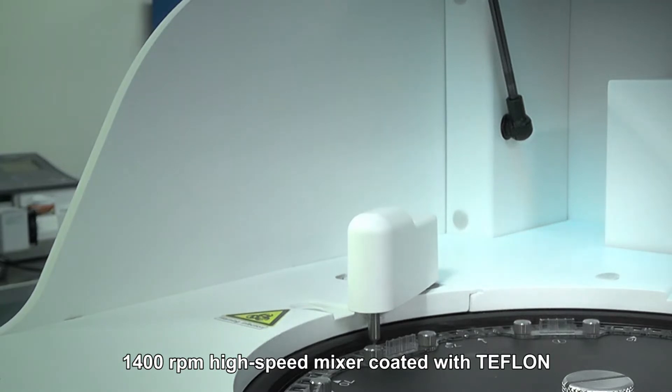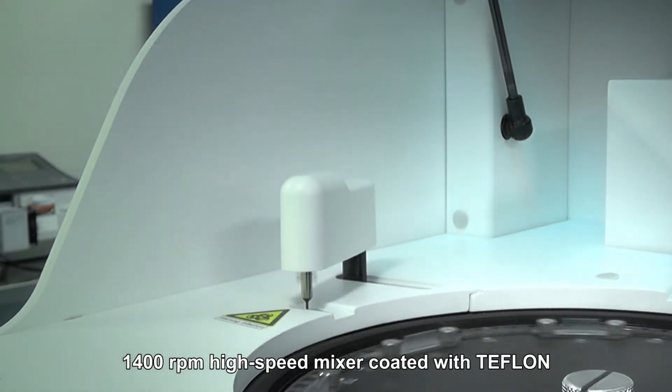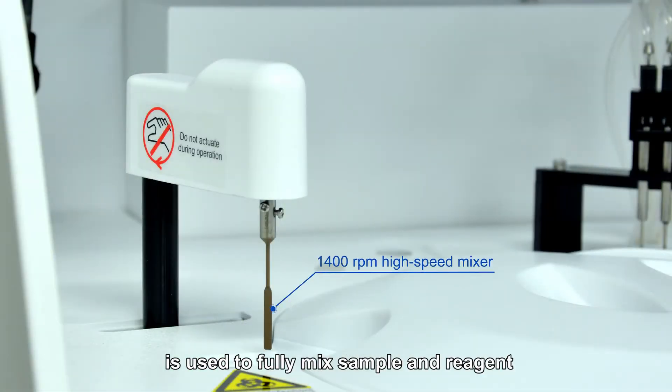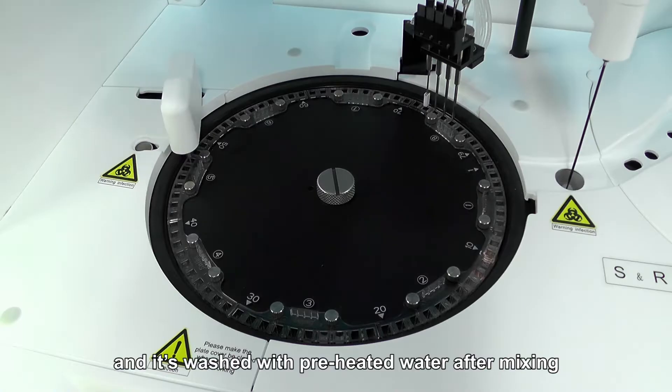1,400 RPM high-speed mixer coated with Teflon is used to fully mix sample and reagent and is washed with preheated water before and after mixing.